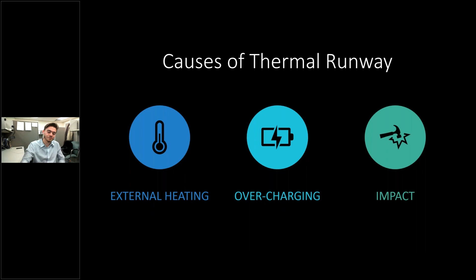So when installing a battery, it's very important to treat it very carefully, because any damage, such as dents to the side of a battery, can result in damage to the separator plate within the battery. And if there's damage to the separator plate, you'll have issues regulating current, which could then lead to more temperature that will increase outside of its operating temperature and lead to thermal runaway.